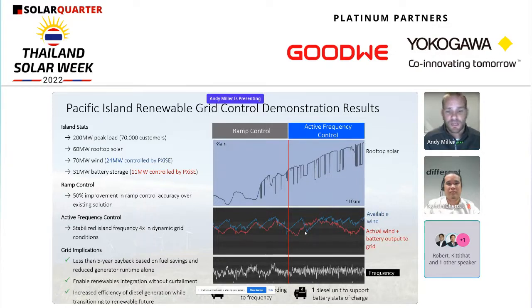The initial use case we were deployed to address is managing the ramp control requirements for the wind asset. On the left-hand side of this diagram, we're managing the available wind and using the battery to shape that to meet a specific requirement, slowing the rate of change into the power grid so the system would maintain stability. Through our high speed and accurate control, we demonstrated over a 50% improvement in ramp rate control, meeting all the ramping requirements, which has real benefit for the power grid.